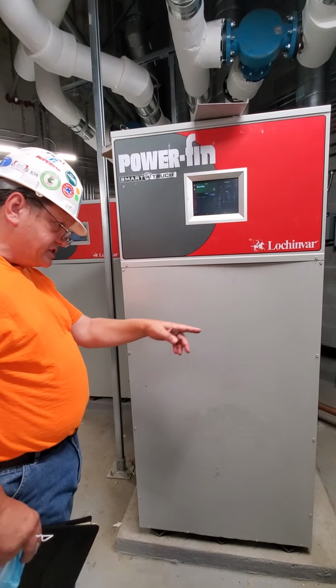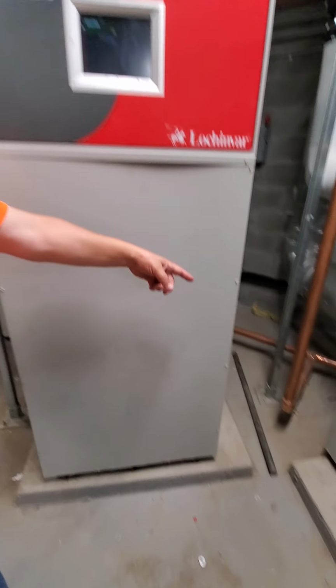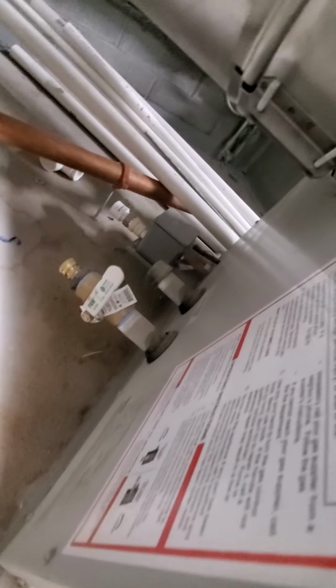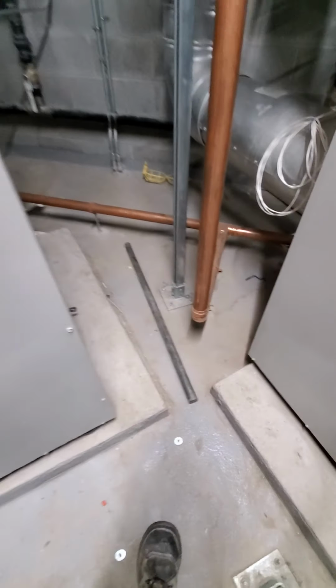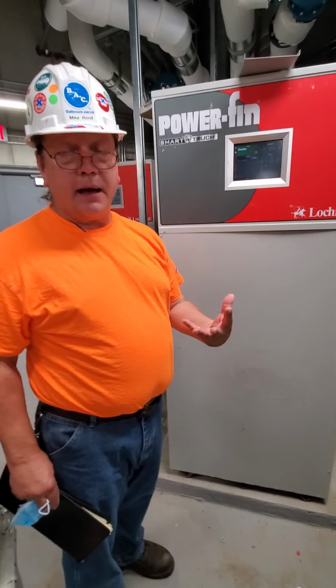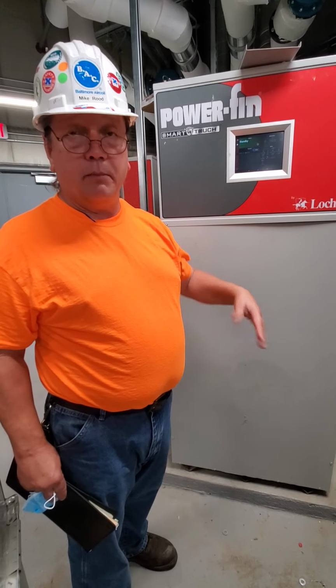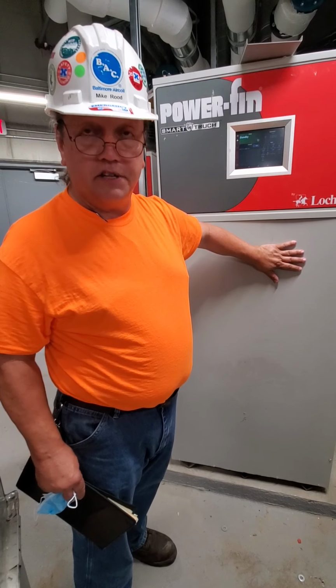There's also a condensate drain on the back of each one, and there's a little gray box down there where the cover needs to be taken off the top, and that needs to be rinsed out. You notice the drain is not connected. You should not have water coming out that drain. Even though it's a condensate trap, there should not be any water coming out because these are not condensing boilers.